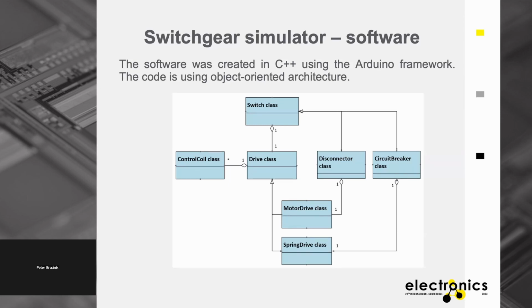So we wanted to simulate this effect. This class represents the small time of activation or activity when the switching or closing is activated, and at the same time it controls the energy that is stored. If you make too many switching operations with the circuit breaker, you will lose the energy that is in torsion, and you won't be able to operate the circuit breaker anymore until you use some motor that will create this torsion again.